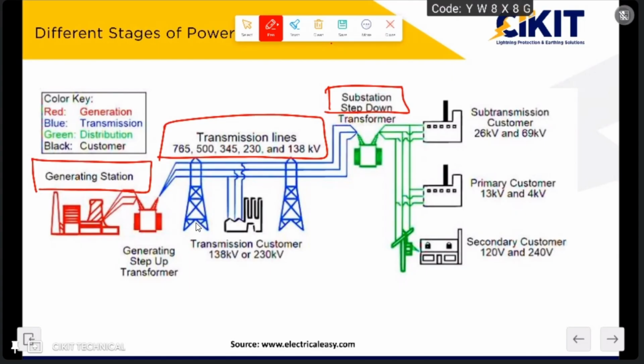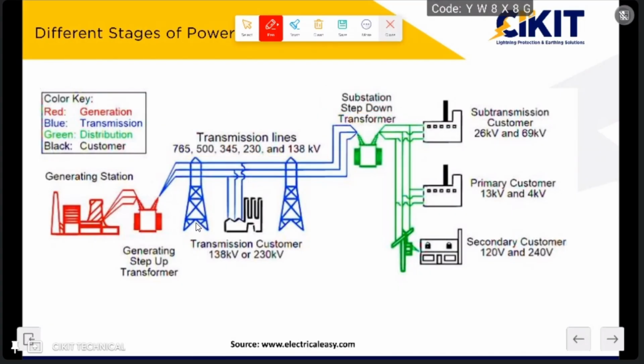So the power rating of the substation will be very much higher, and the fault current rating of the equipment in the substation also will be very much higher. In our industry, if any equipment fails, it will result in the loss of production for this particular wing alone. But if any equipment in the substation fails, and 100 industries are fed from it, all 100 industries won't receive the power supply. So any failure in the substation will result in loss of service to all the industries receiving power from that substation. So substations are very much essential, and a failure in a substation will result in loss of service to the entire area also.